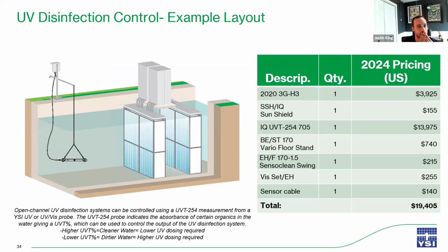So this is an example of a typical layout where we've got a UVT 254 probe a little bit upstream from a UV disinfection channel. And what we're measuring here is UV transmittance percentage, so the amount of UV light that can be transmitted from one side of the probe to the other side, where we detect that and determine the transmittance level. When this probe ties into a UV disinfection system, it gives that UV system a heads up on how clean or dirty the water is based off of the UVT value.